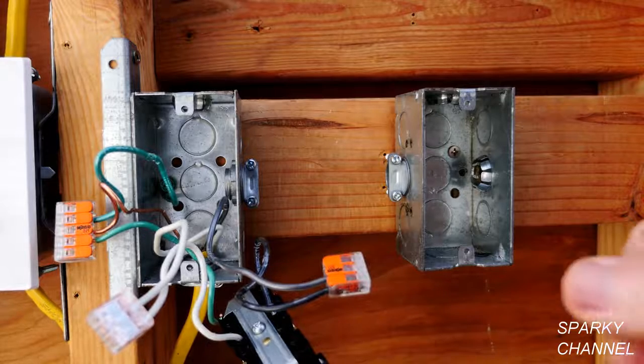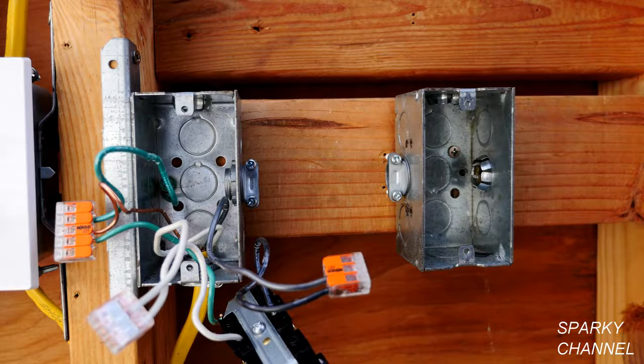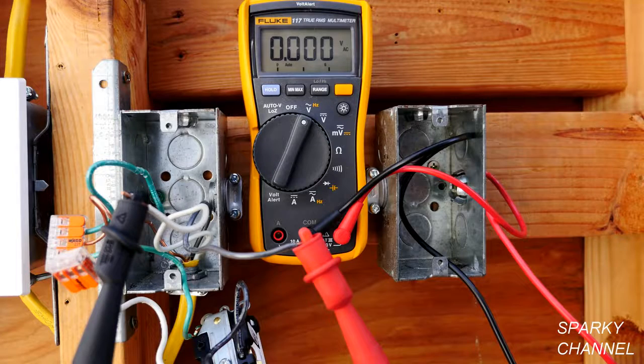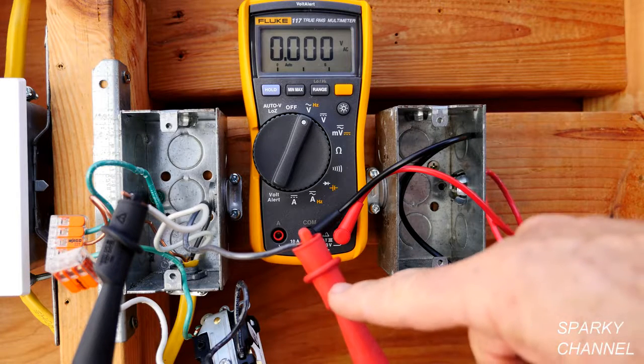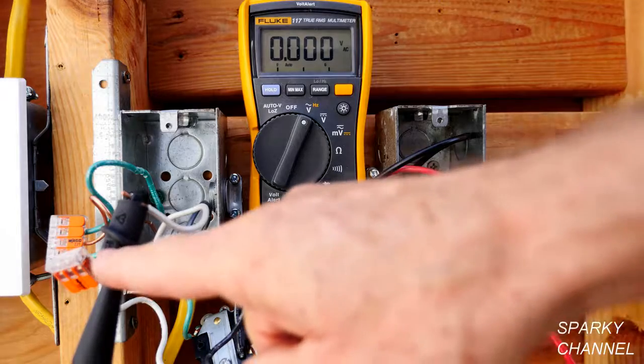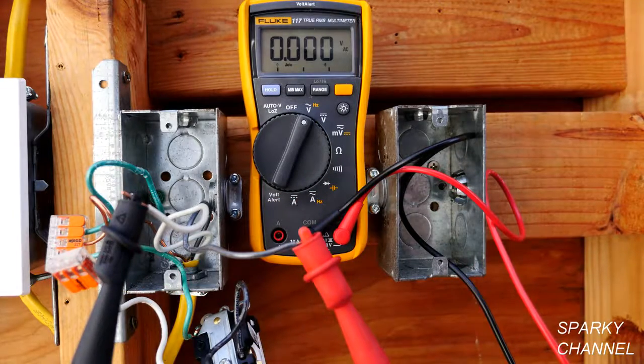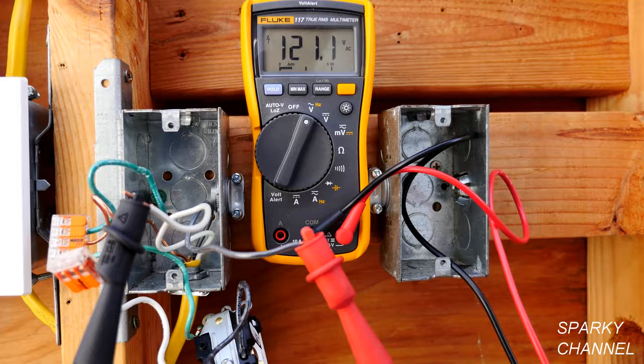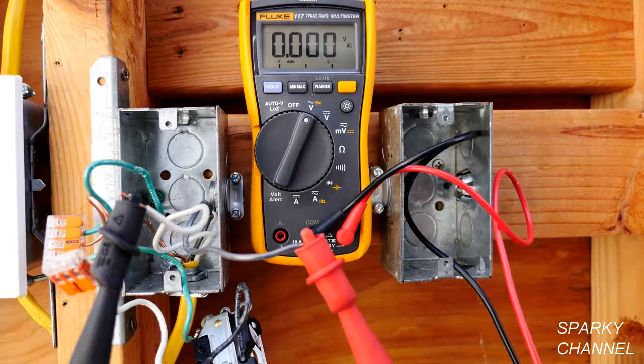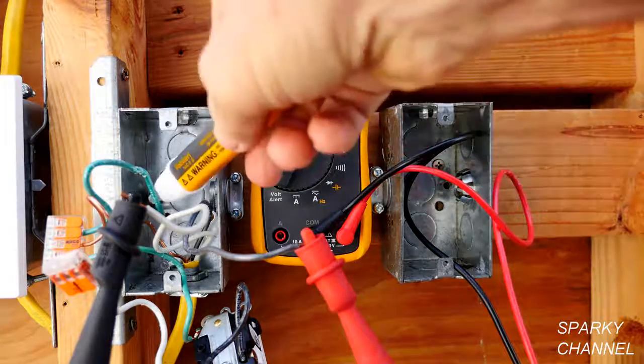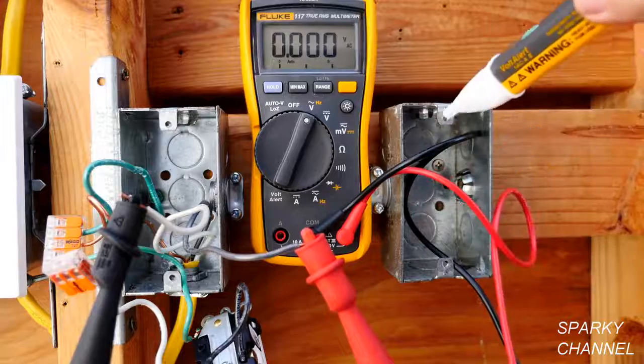But before proceeding further, I'd like to do another test, and that is simply test for voltage. I've set up my digital multimeter, and I've got one lead on the black wire and one lead on the white neutral wire of the cable that brings the energy into the box. And I'm just going to temporarily turn on the circuit breaker. Okay, the circuit breaker is temporarily on, and we have 121 volts, so that's very sufficient voltage. I've got the circuit breaker off now, and the digital multimeter says that the voltage is off. And I'll just double check real quick with my voltage detector, make sure nothing's hot.